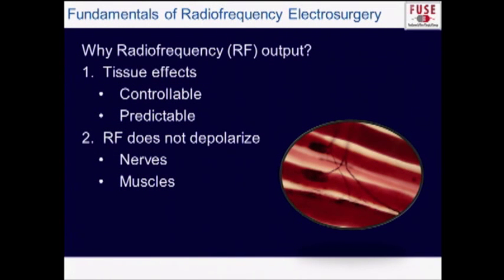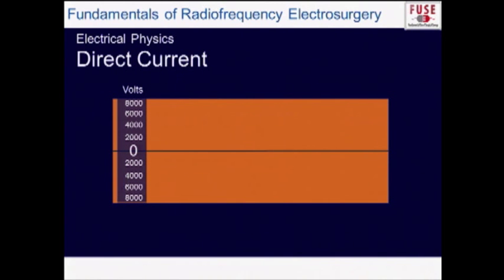Why do we use RF? RF is quite controllable and predictable as long as you understand what you're using. At above 100,000 Hz or 100 kHz, it doesn't depolarize nerves and doesn't depolarize muscle. That's why your patient doesn't go into cardiac arrest when this energy passes through them — it's a very interesting energy source in that regard.